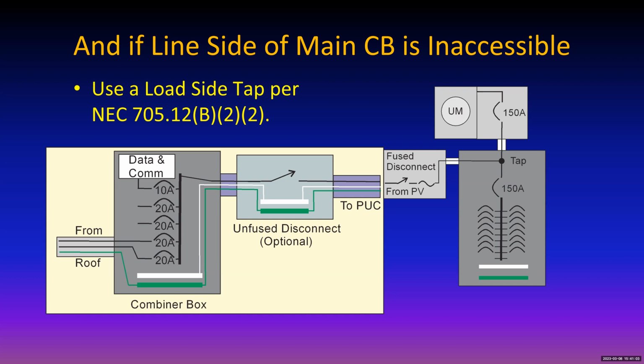Current doesn't go backwards into the PV system. The PV system is a source, so you only get power out of it unless you get a short circuit there and the system fails, and that's why you've got fuses there. That fuse disconnect never blows because the PV system did something wrong. It's because maybe the PV system had a short circuit in an inverter, and then it's the current that comes from the utility that blows that fuse, not the current from the PV. PV is never going to blow that fuse because that fuse is sized at least 125% higher than the maximum current that's ever going to come out of the PV system.